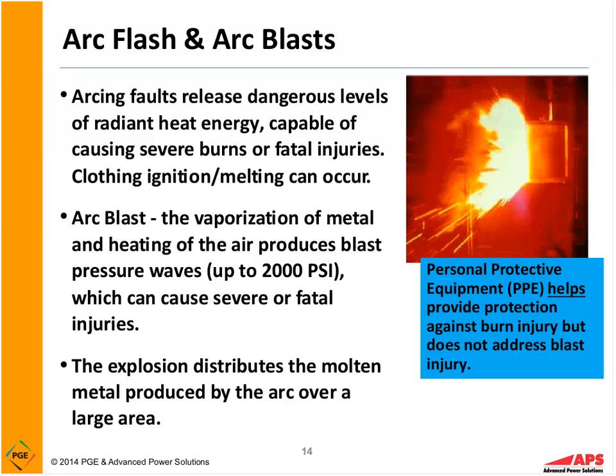The explosion distributes the molten metal produced by the arc over a large area. So just standing to the side, if we have a lot of energy, won't protect you, or possibly just putting a lab coat on when the arc blows down underneath that lab coat. Now, when we look at personal protective equipment for shock and arc blast, it helps provide protection against burn injury but does nothing against bodily damage due to the blast pressure wave.